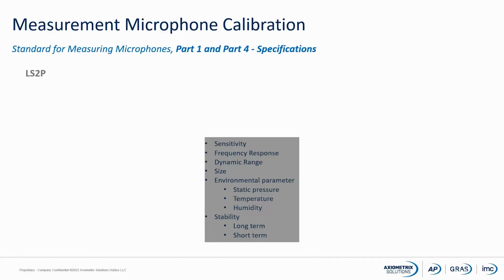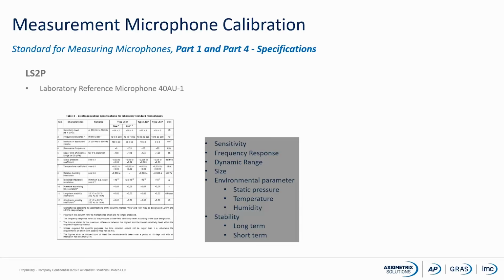If we look at the laboratory part of the standard, part 1, LS means laboratory, and 2 means it's a half-inch microphone, and P is the type of the microphone. P for pressure, F for free field, and R for random incidence microphone. A laboratory reference microphone like the GRAS 40AU, and if you would like to make a reference microphone, then you have to fulfill all these parameters written in the standard.